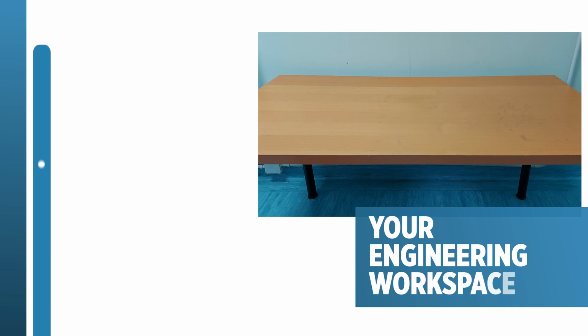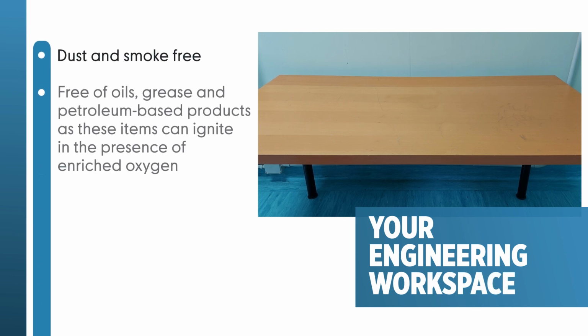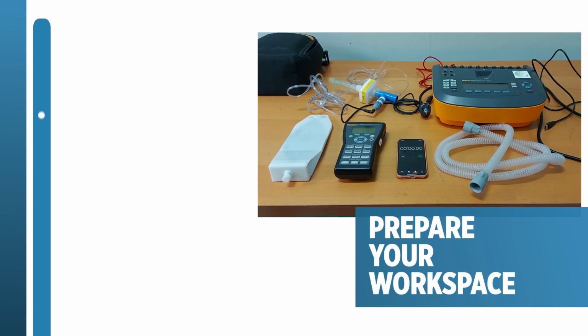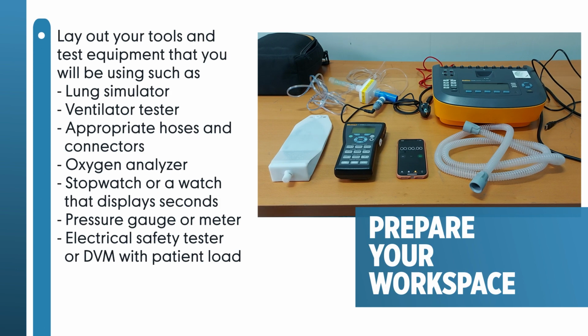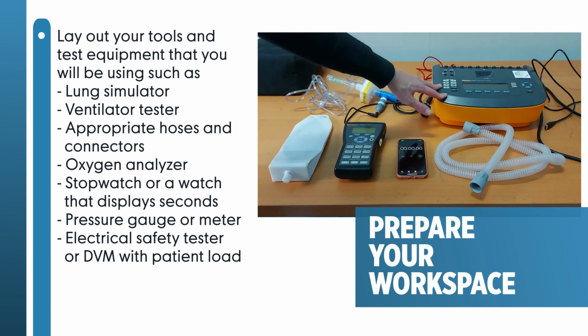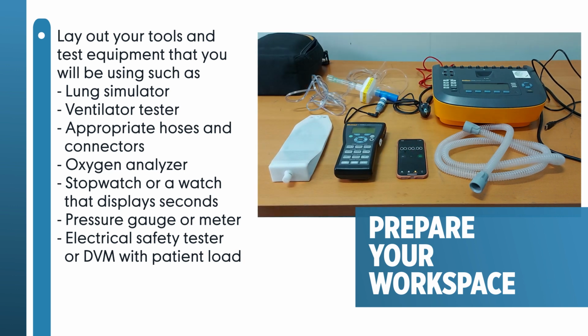Regardless of where you are working, your workspace should be clean, free of dust, and smoke-free. It must also be free of any oils, grease, and petroleum-based products, as these substances can ignite in the presence of enriched oxygen. Prepare your workspace by laying out your tools and test equipment that you will be using, such as lung simulator, ventilator tester if available, appropriate hoses and connectors, oxygen analyzer, stopwatch or a watch that displays seconds, pressure gauge or meter, and electrical safety tester if available, or DVM with patient load.